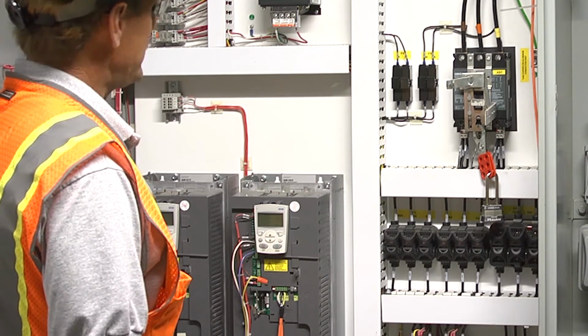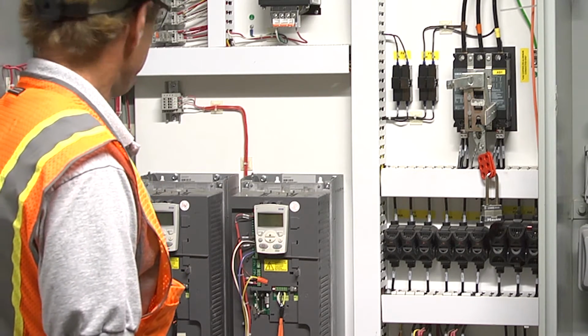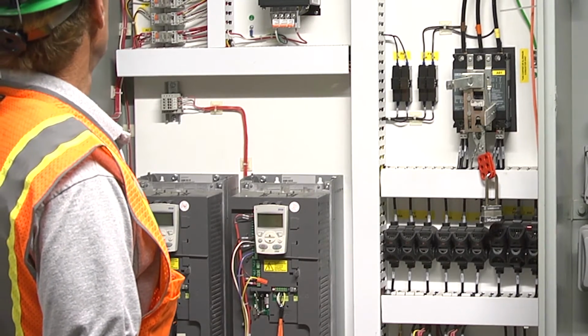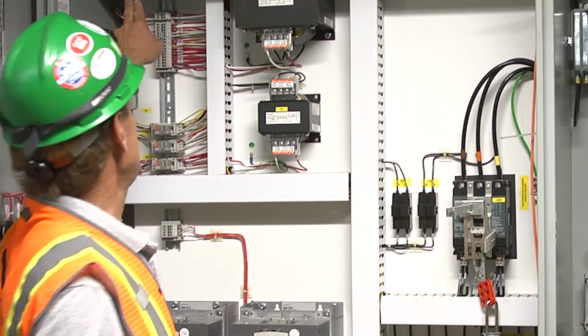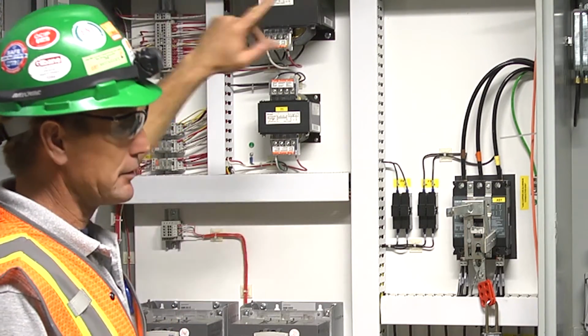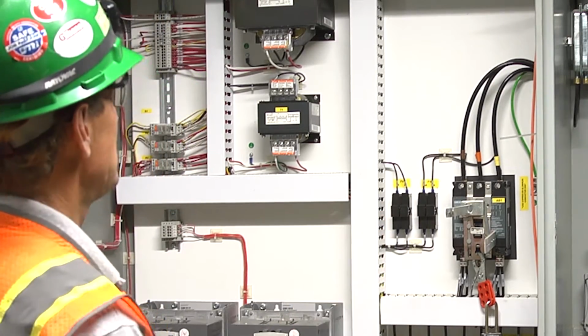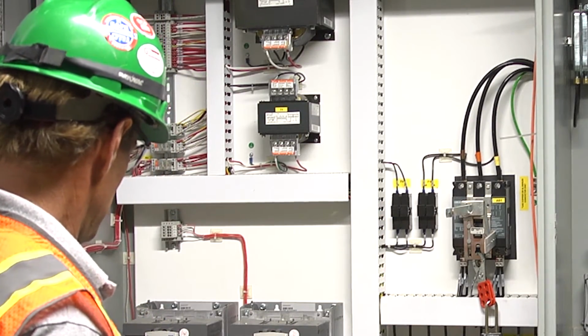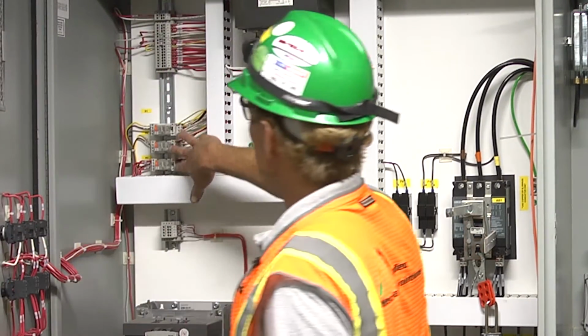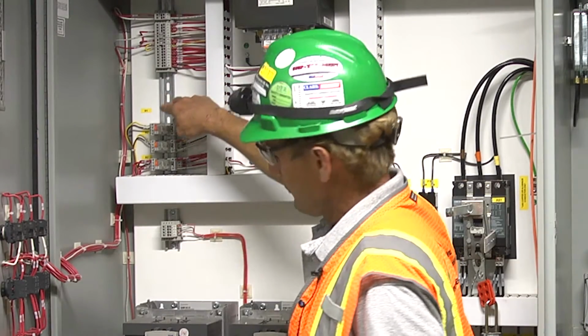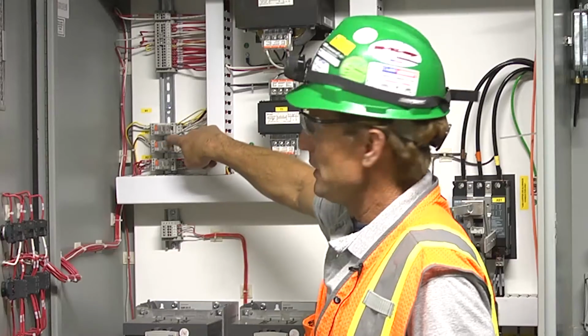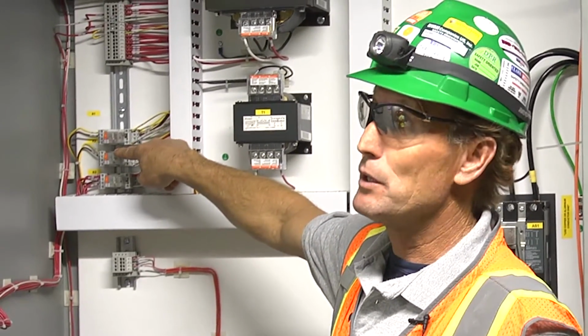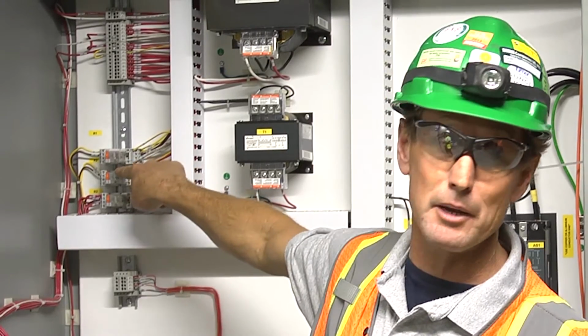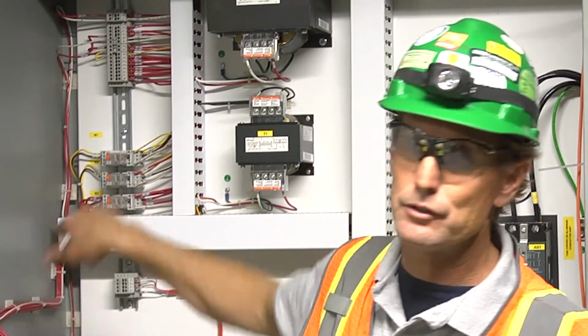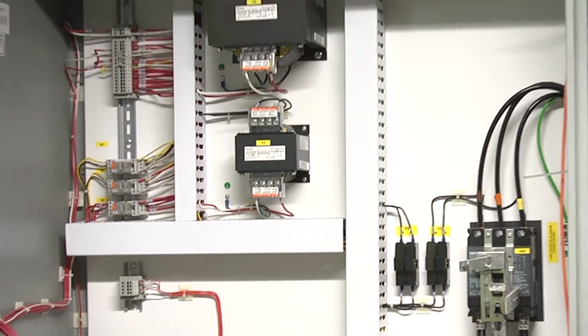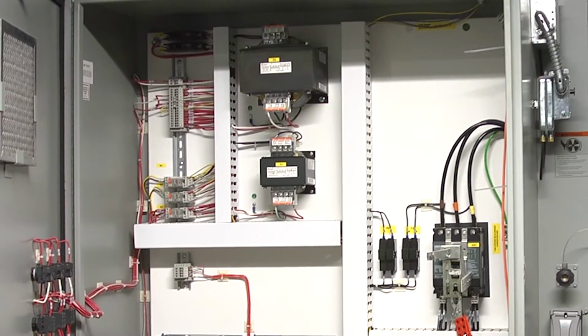And then of course your control voltage transformers above. And your 110 circuit breakers above here are for your lighting circuit and your door switches, safety switches, and such. These 3 relays here provide the safety interlock, and then the second one is for the start-stop from the building automation system, I believe. And then the last one is for the door switch safeties. So, okay, that's pretty much it for the single source power panel.